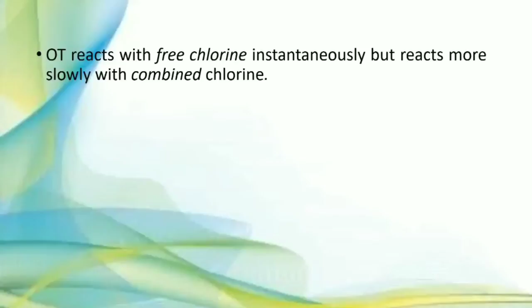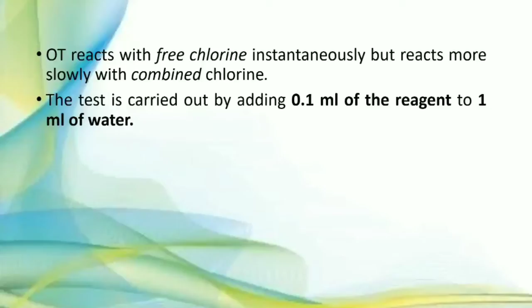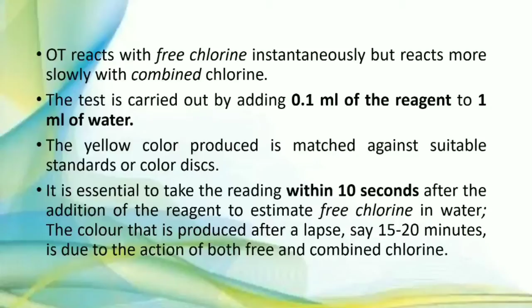This is the kit of the OT test. The test is carried out by adding 0.1 ml of orthotolidine to 1 ml of water, and that color is matched with a standard disk, and the reading should be taken within 10 seconds. The second test is the orthotolidine arsenite test. This is a modification of the OT test to determine free and combined chlorine separately. In the first test, if the water contains nitrites, iron, and manganese, they also produce yellow color.